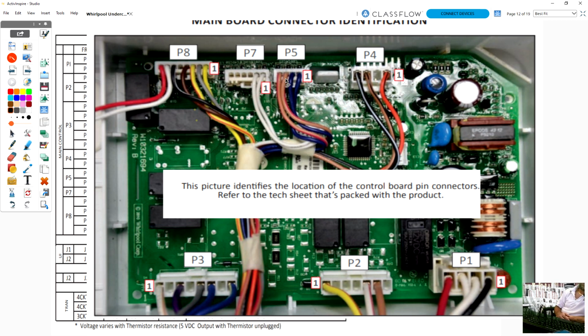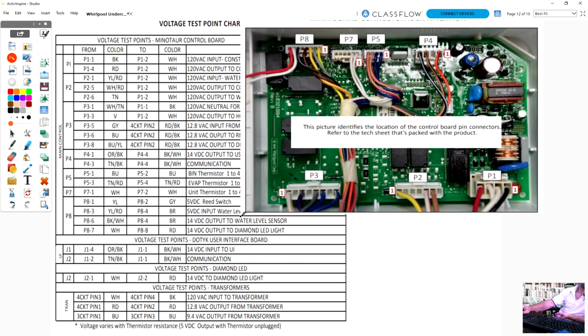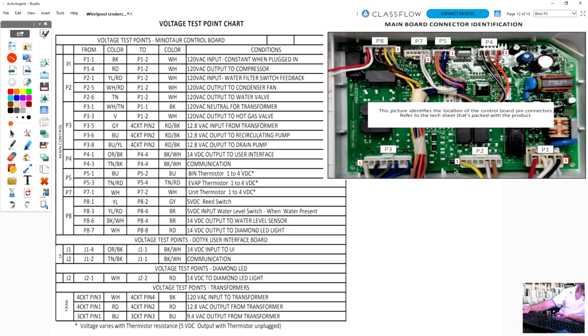Now, the evaporator thermistor is plugged in underneath the unit. It might be easier to get to just the plug of the evaporator and bin thermistor directly to check that out. But in order to check voltages, you have to go to the main board. You will not be able to unplug the thermistor and then make that voltage test, because if you unplug the thermistor, the board would not see it and would initiate an error or fault, and probably stop the ice maker from working.